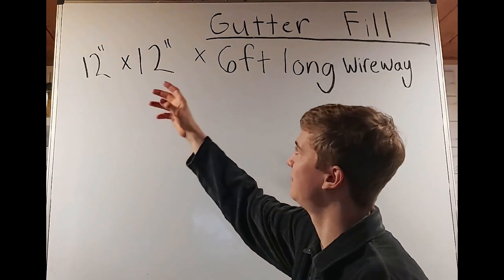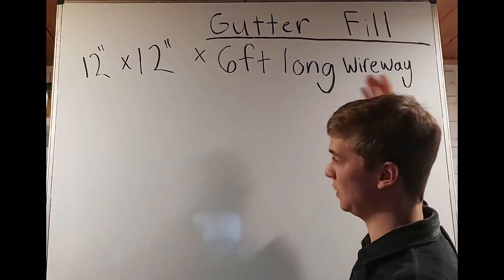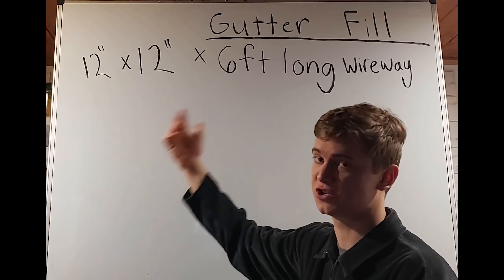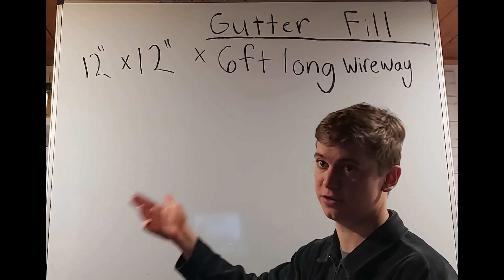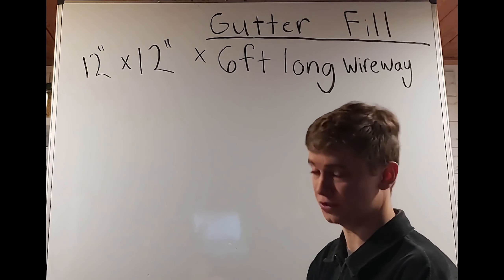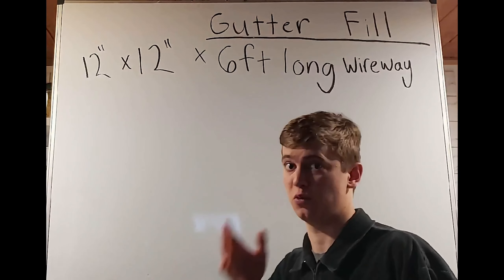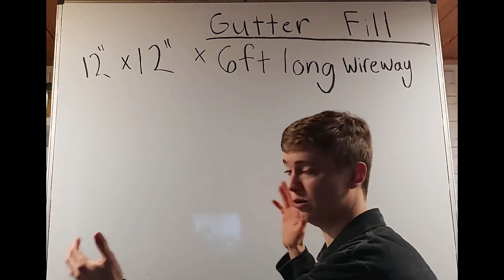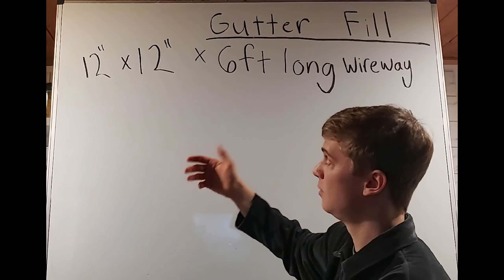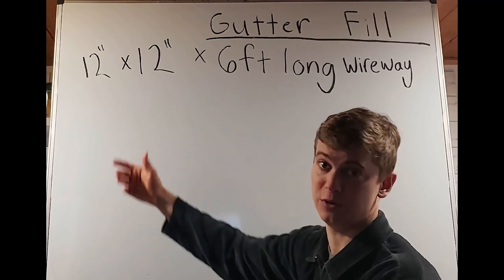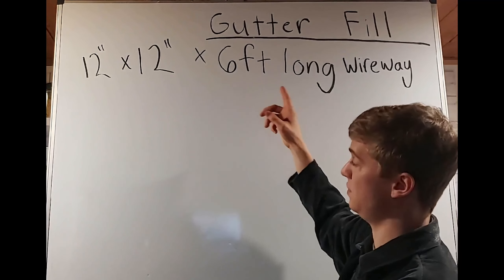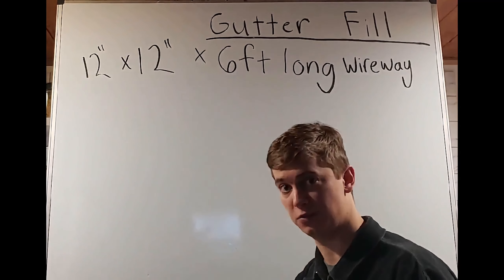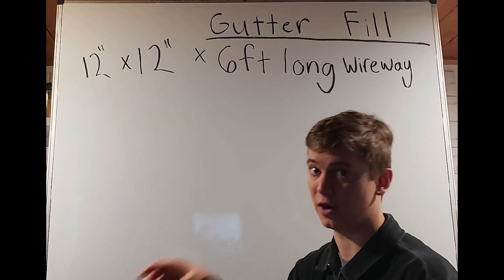First question: we have a 12-inch by 12-inch by 6-foot-long wireway. We're already working with inches, which is what we want because we're going for square inches. Just be mindful that we're working with square inches, so we only have two dimensions — we're not using how long it is, so we can eliminate the 6-foot length. We already know it's 12 by 12. If you have something that's 12 inches by 12 inches and you multiply 12 by 12, you have 144 square inches.